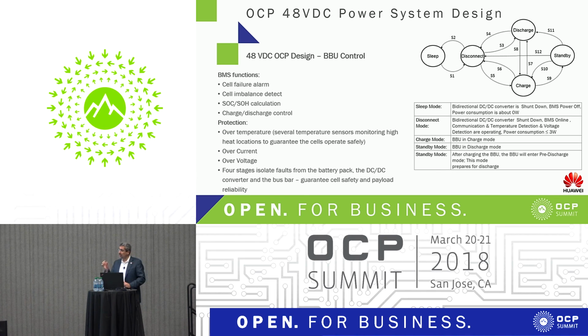The DC-to-DC converter is also very important. It allows us to use basically any sort of bank of batteries, where the cell voltage may add up to 60 volts or 70 volts, it really doesn't matter, because we use the DC-to-DC converter to control the output to exactly whatever we set it to, which in this case is like 52 volts. We do that because when we lose AC power, it was at 54, we want to see that voltage drop until it reaches 52, and then say, hey, we're out of power, batteries have to go into discharge mode. Having that 2-volt difference allows us the time to see the event happen and then go into discharge mode. But the DC-to-DC converter will then hold 52 volts regardless of what the voltage in the batteries is doing. So that makes it a very safe output for the equipment, you don't have to worry about voltage spikes or anything coming through our system because we have a DC-to-DC converter.